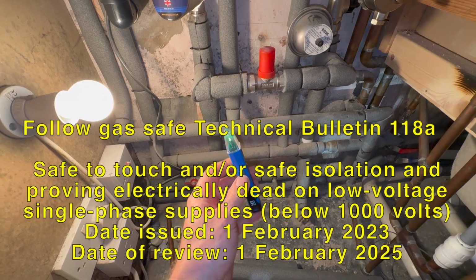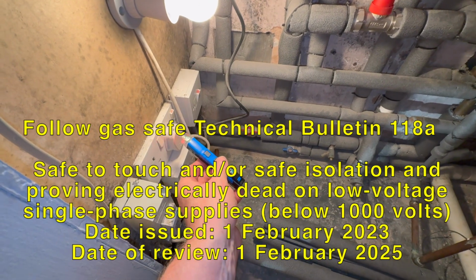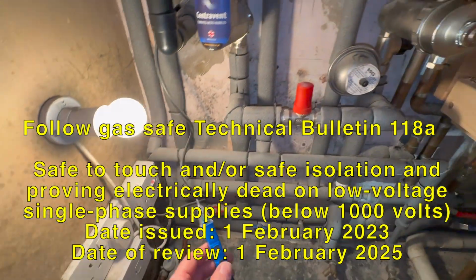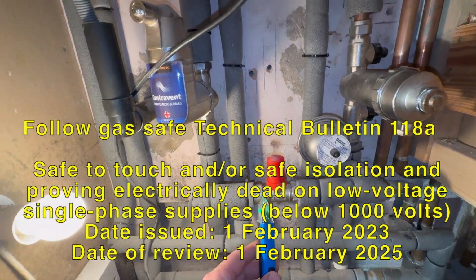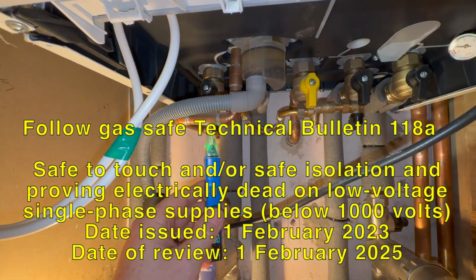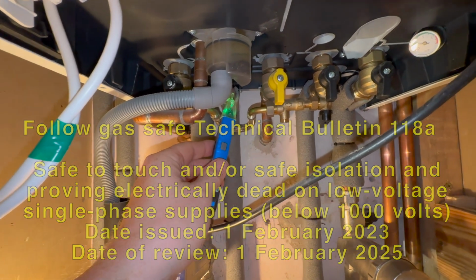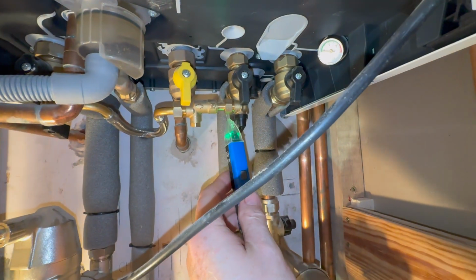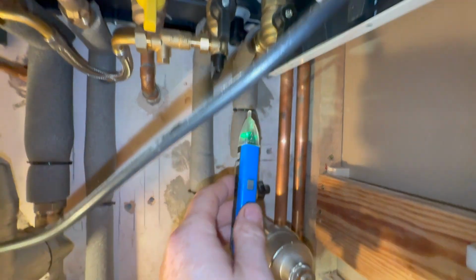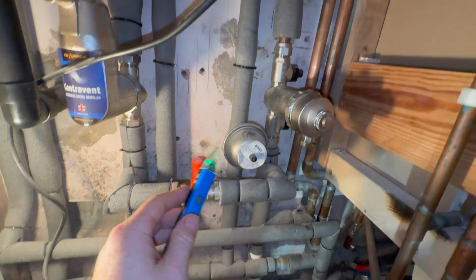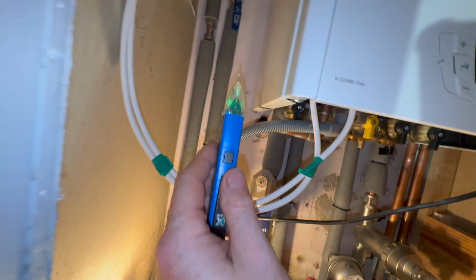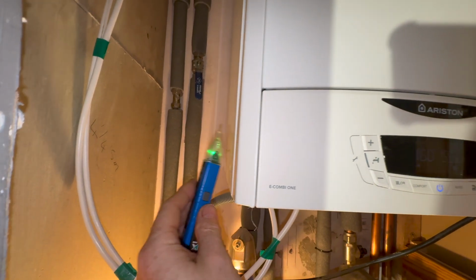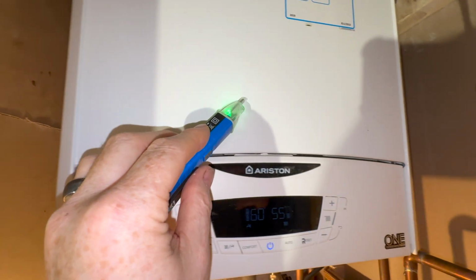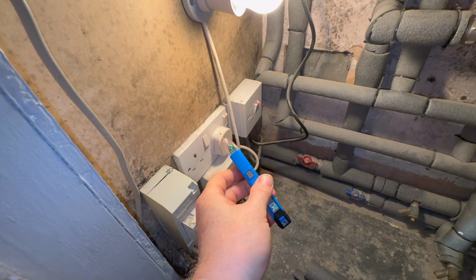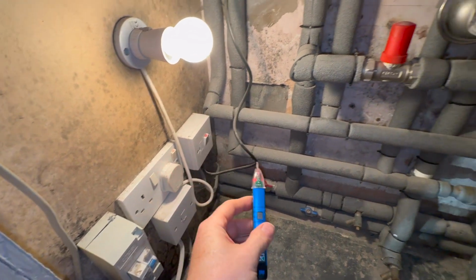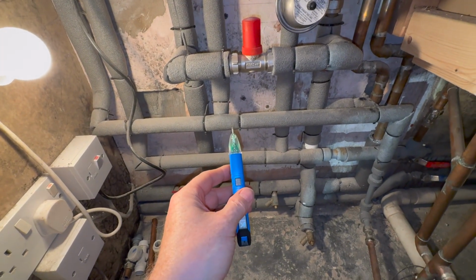Turn on, make sure it's working, use it at a known supply, and then check anything metal around the boiler. Check the casing. Back to your known supply. So everything should be okay for me to touch now.